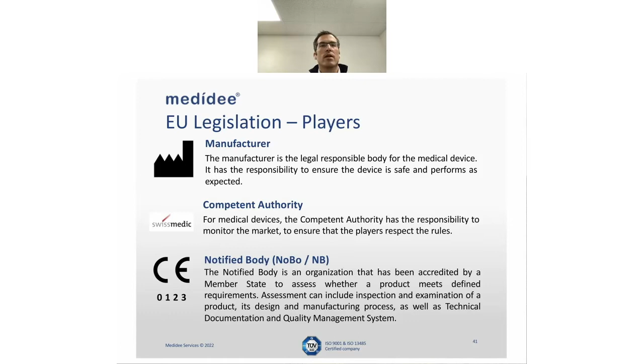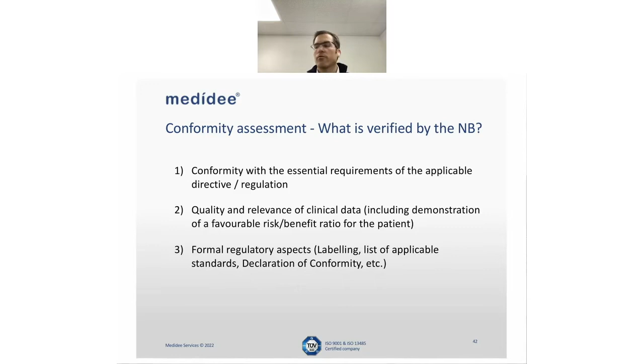In this conformity assessment, what is actually checked by the notified body? What they are going to look at is typically if you are able to address the famous 123 requirements in Annex 1. So how do you address those requirements? Is your device clinically safe? Basically, at the end of the day, when we use your device, do we have a positive risk-benefit ratio for the patient? All the data that you have to sustain the performance and safety of your device will be reviewed in detail. And then there is a formal regulatory aspect that will be checked: typically the way you label your device, what standards you use, how you make the declaration of conformity, and so on and so forth.